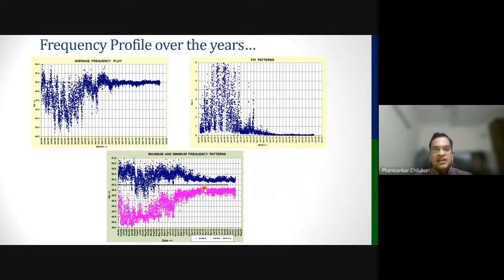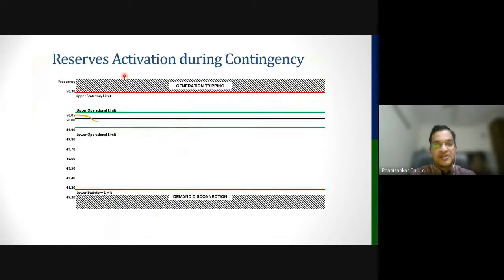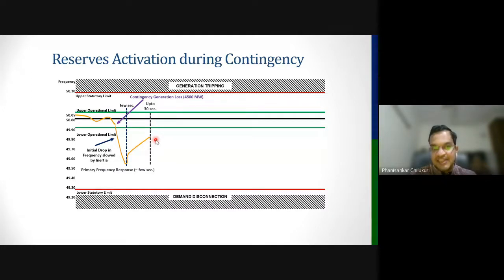This has been possible because of several interventions. We have talked about the frequency control continuum, right? Different interventions, right from ABT, then DSM, RRAS, AGC, have all contributed, along with good forecasting, portfolio management and so on. After any contingency or sudden generation loss, first the inertial response slows down the initial rate of change of frequency. After that, the primary frequency response brings the frequency to a quasi-steady state through governor action. And AGC then picks up to replenish the primary frequency control so that we are ready for the next contingency.